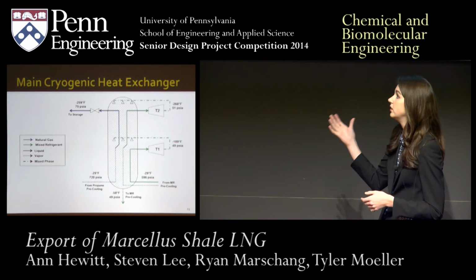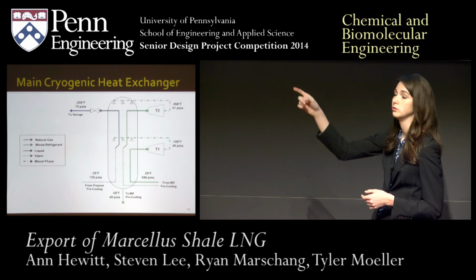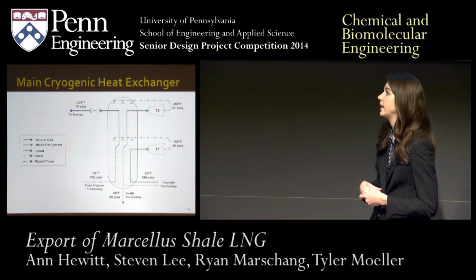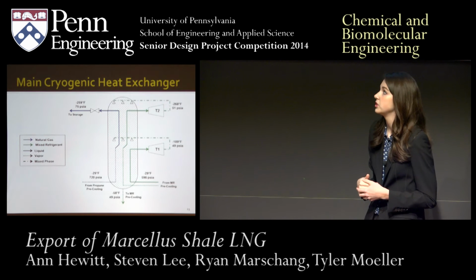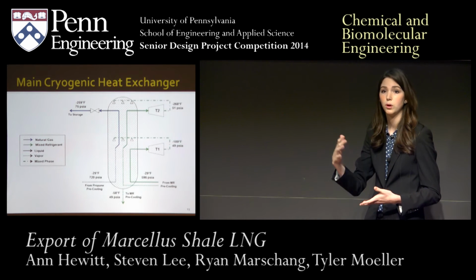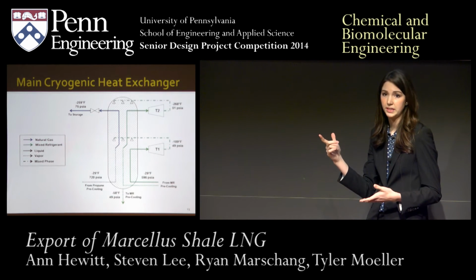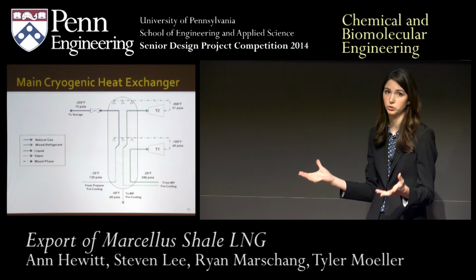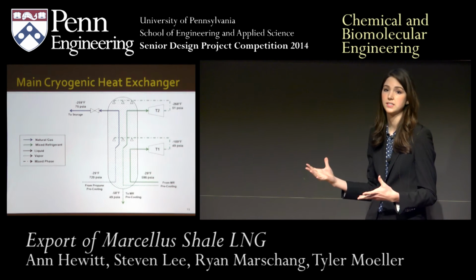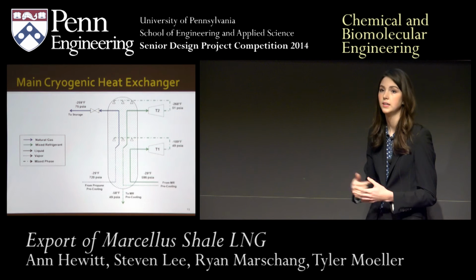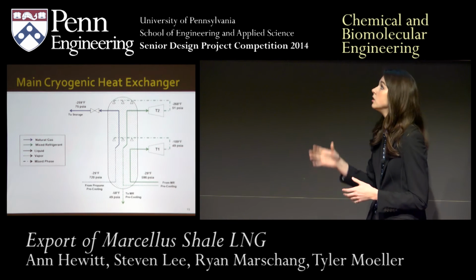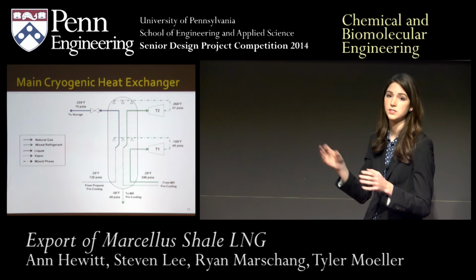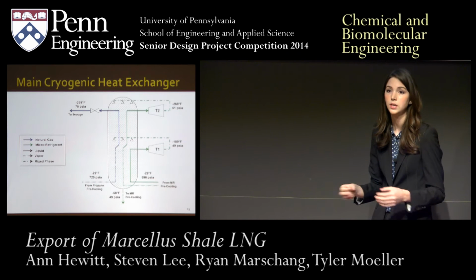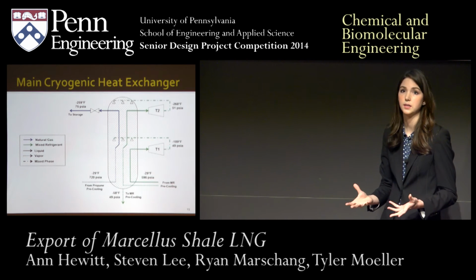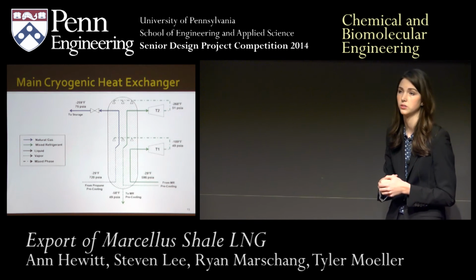We first follow the liquid mixed refrigerant stream, which is the solid green line coming in from the right. The liquid mixed refrigerant rises up through the bottom half through the warm bundle, exits about halfway up our heat exchanger, and is then expanded and cooled through a turbine. This also generates some power for our process that we can feed back in. This cooled stream, which is mostly liquid, is then sprayed down over the warm bundle, cooling the components in the tubes rising up through that bundle.